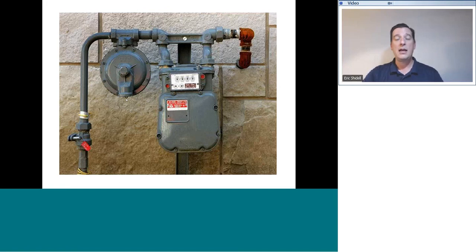So if the pressure that regulator is controlling to is 7 inches of water column, what that really means is 7 inches of water column higher than the atmospheric pressure outside. The vent, which in this regulator is right down here at the bottom, is exposing the regulator to atmospheric pressure. So it always knows to send out 7 inches of water column greater than whatever the pressure is right here. As a result, through the normal operation of the gas regulator, a little bit of natural gas can and will escape from that vent. So it is normal to be able to smell and detect natural gas in this location.